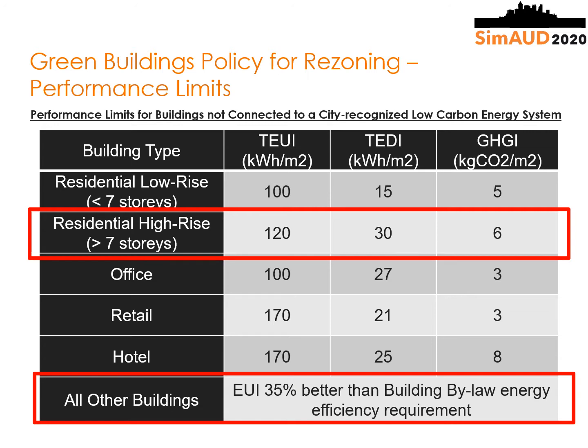For the residential high-rise, it has to meet a TEUI of 120, a TEDI of 30, and a GHGI of 6. And for the recreational part, it has to meet 35% better EUI than the building bylaw energy efficiency requirement, and that is ASHRAE 90.1 2016.